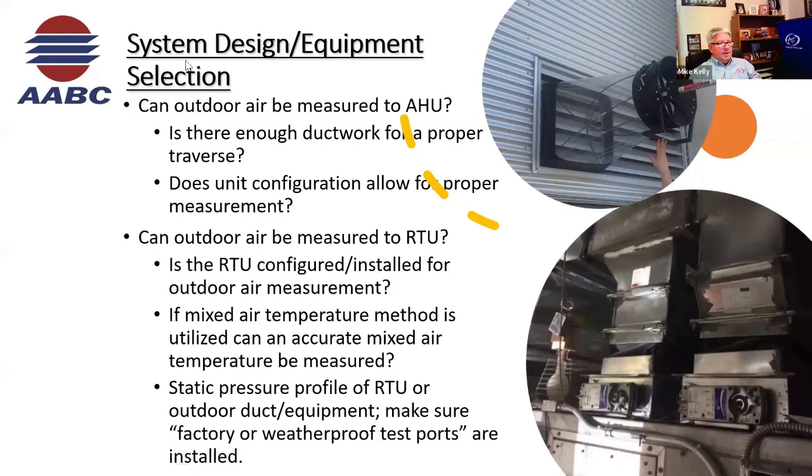Okay, system design selection. We threw this in there because we've seen things. Over here to the right, you'll see someone holding a capture flow hood over an outside air louver. Does anybody really ever want to see that? I mean, if that's all you got and everybody's going to buy into it, okay. But not on my building, not something I would want done. I know what I'm looking at for airflow, but there's so much correction here and factor for error. Mind blowing.